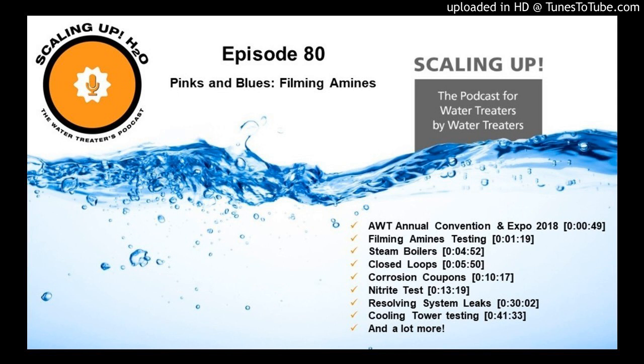We had so much iron in the water, we diluted it so many times, and I'm not even going to guess how many. We diluted it so many times and we still could not get a proper iron residual in the system. So we just said, hey, there's a lot of iron in the system, and we, of course, needed to flush that out. So we thought we were right there. We could start running the test at 3,000 ppm. Of course, we went back to 0 and we had this orange looking water.